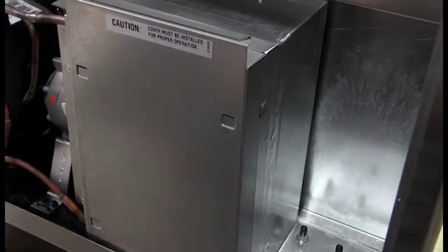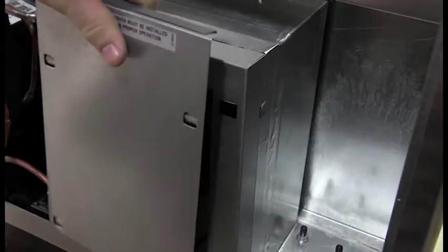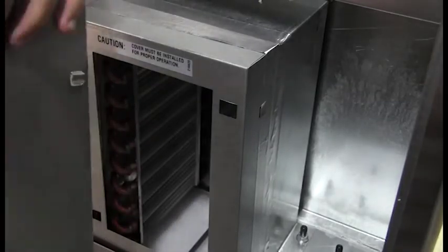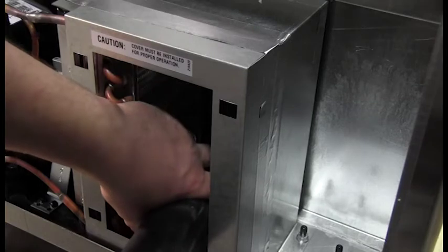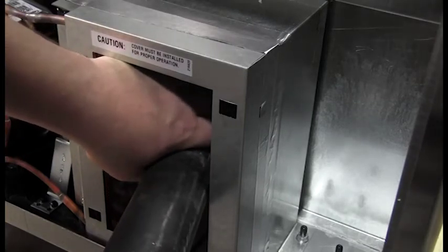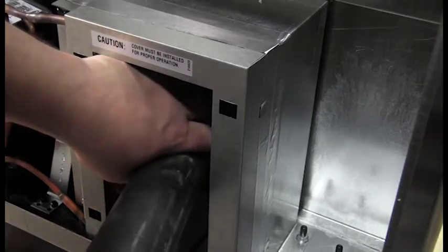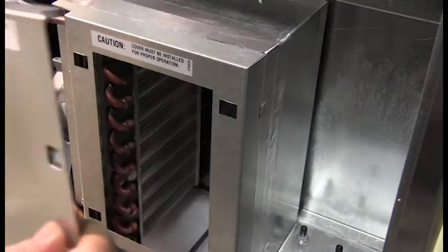The condenser is located on the bottom right hand side of the unit. Remove condenser panel by lifting up. Clean the condenser with a vacuum or soft brush. Be very careful not to bend the fins. And then replace the cover.